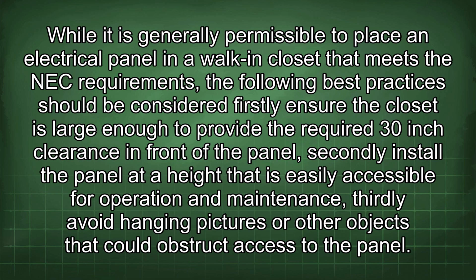Firstly, ensure the closet is large enough to provide the required 30-inch clearance in front of the panel. Secondly, install the panel at a height that is easily accessible for operation and maintenance. Thirdly, avoid hanging pictures or other objects that could obstruct access to the panel.